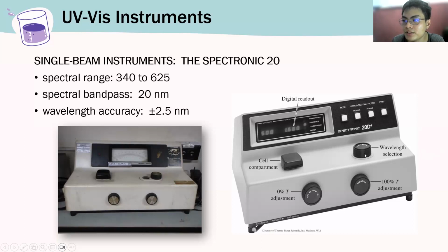And sabi ko nga sa inyo, yung wavelength selector, ina-adjust yan either manually or electronically. So sa photometers, ikaw mismo yung mag-a-adjust. Yung mga echelon grating dyan, tinatwist yan, and then yung grating, mag-change ng angle. And as it changes the angle, ibang wavelength yung magpapass through sa sample. Parang CD lang. When you change the angle, ibang kulay yung nakikita nyo.